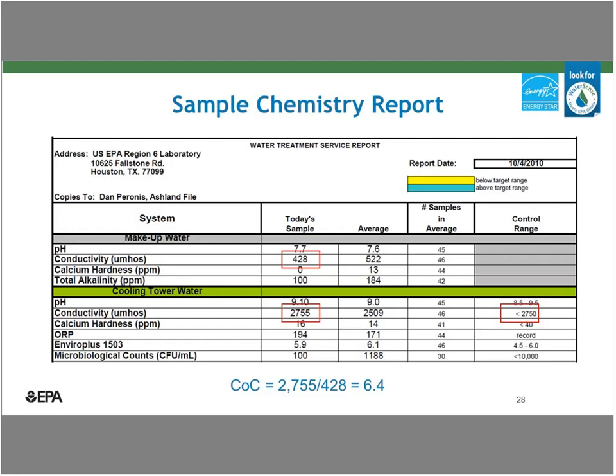One thing to also be aware of is where your conductivity sits with respect to the control points. In this case, it's right at the upper limit, which is where you want to be. But if the conductivity of your cooling tower water is significantly lower than the set point, you might want to investigate a leak or some other problem that may be occurring.